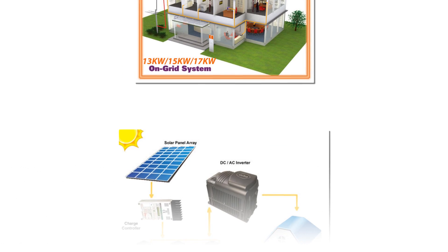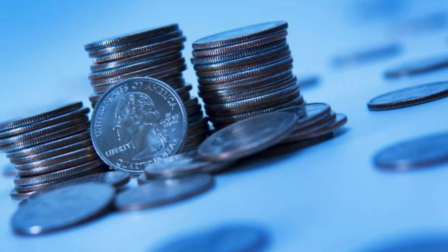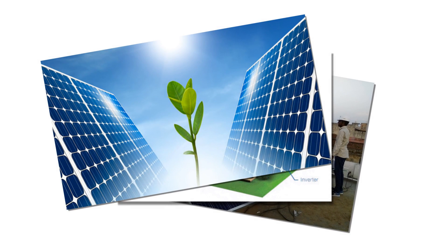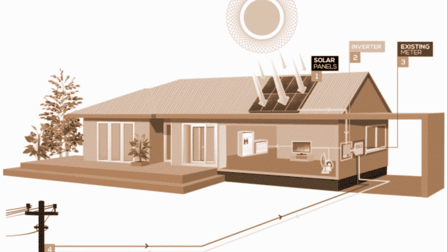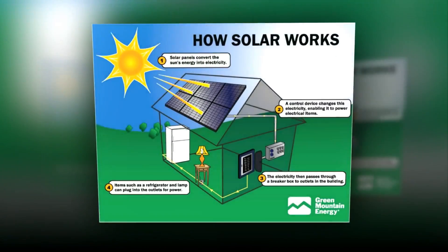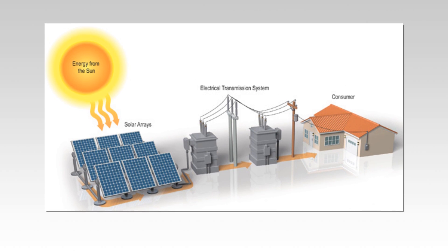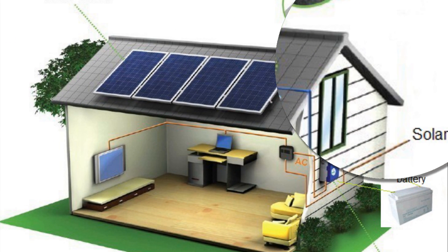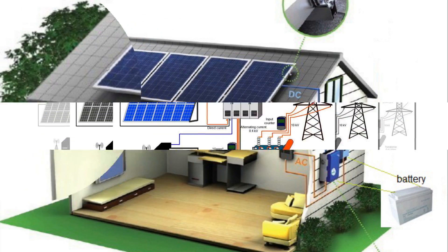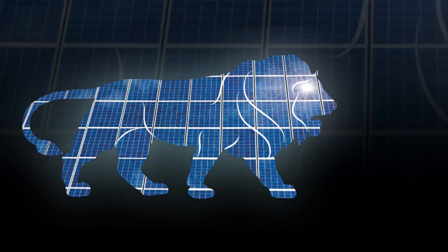Let us understand this with a simple example. A 5kWp grid-connected solar power plant installed at a user's rooftop is expected to produce 4–5 units per kilowatt per day, so a 5kWp solar plant will produce at least 20 units per day. In this example, the user's consumption may be 10 units during daytime and a similar amount at night. After providing 10 units to the user's load, the remaining 10 units are fed into the grid during daytime and the same is received back during nighttime. At the end, the user has produced 20 units via the solar system and utilized all 20 units — 10 during the day and 10 at night — with the help of an on-grid inverter and bi-directional net meter.